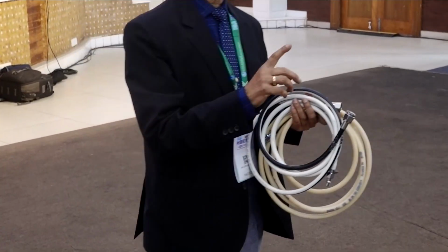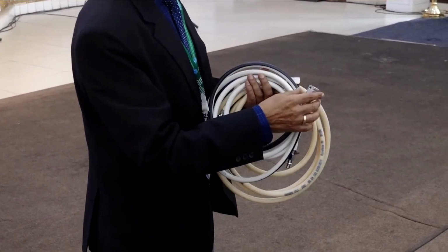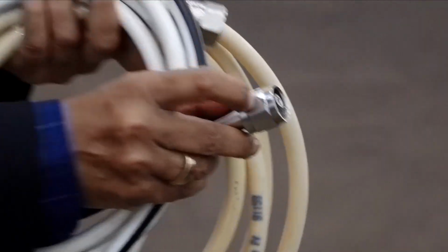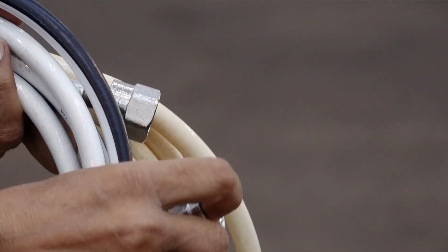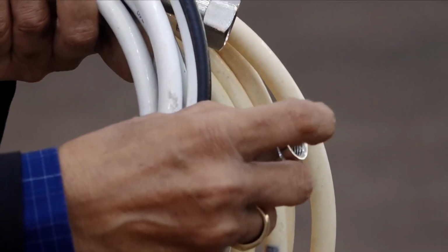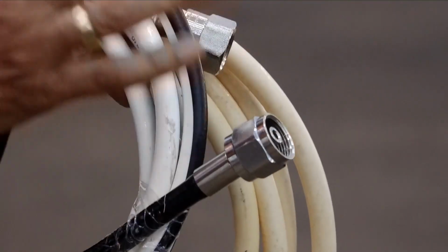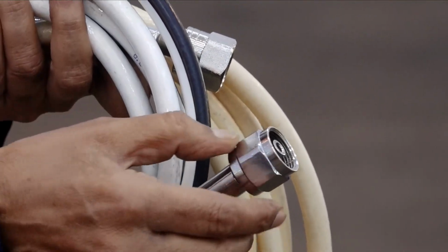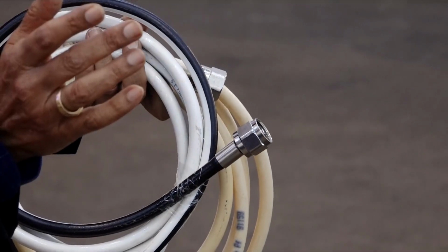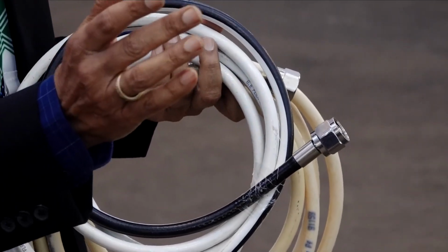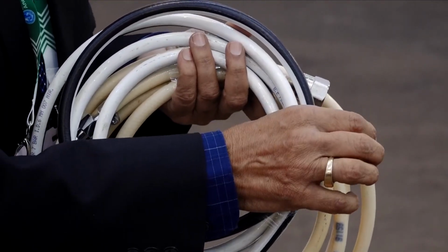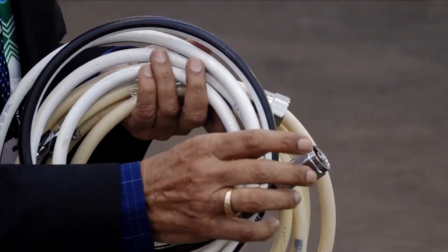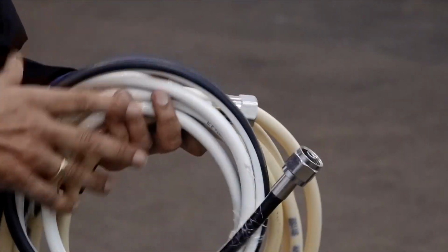The difference between the diameter index safety system and NIST is that in NIST, the screws are not the same diameter for all the gases. It is only the nut or the stem which is diameter indexed. So the British-made machines have NIST, whereas American-made machines have the diameter index safety system. In diameter index, both the nut and the stem are diameter indexed, whereas in NIST it's only the stem. So that is the difference.